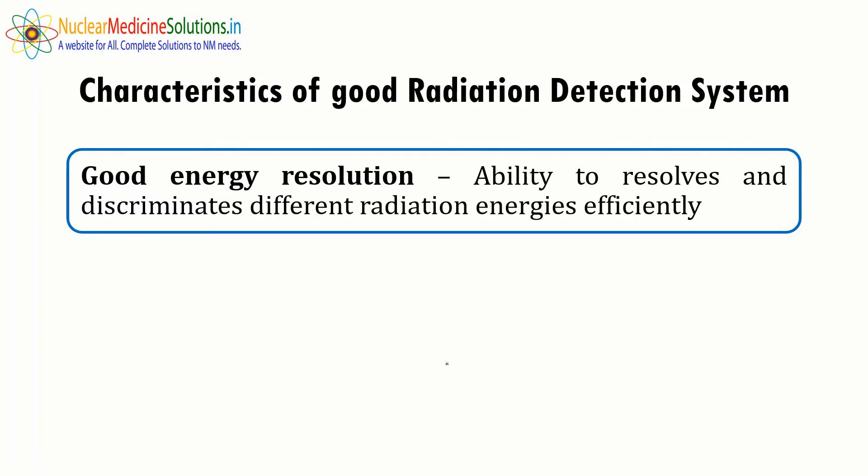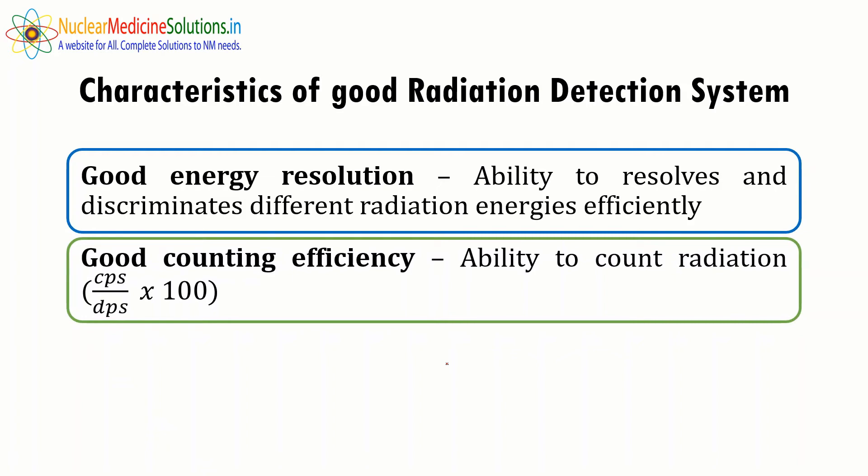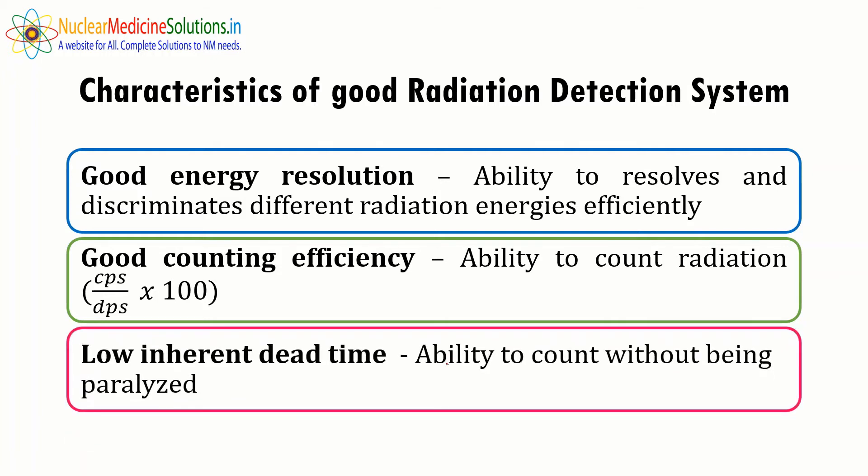The second property is good counting efficiency — the ability to count radiation. In ideal conditions, a good radiation detection system should have 100% efficiency, meaning whatever radiation falls on it should be counted. The formula for calculating radiation efficiency is CPS divided by DPS multiplied by 100 — that is counts per second divided by disintegrations per second, multiplied by 100.